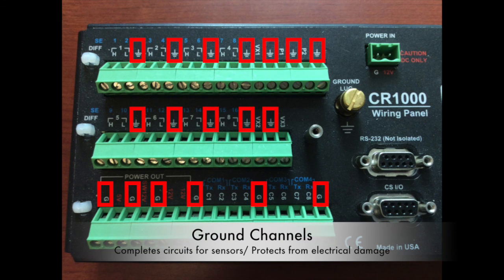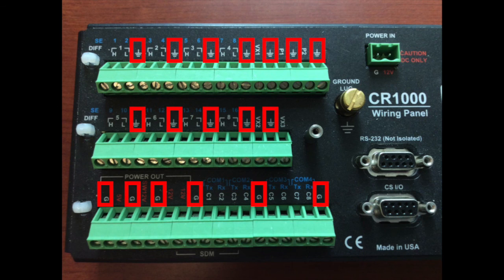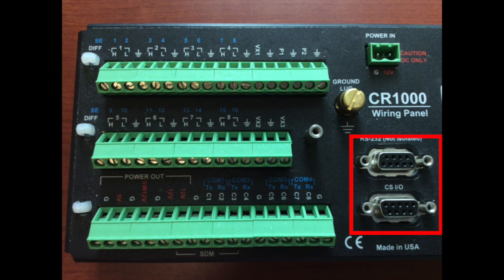Finally, we have ground channels, noted in between the analog channels by a symbol that looks like an inverted Christmas tree, or the letter G on the bottom row for digital grounds. All sensors need ground channels, so when you wire things in, make sure the right cables go into ground channels. The RS-232 and CSIO ports are how the data logger communicates back to us in Raleigh, or how you can check on-site that the values coming in are legitimate and make sense for the parameters being measured.